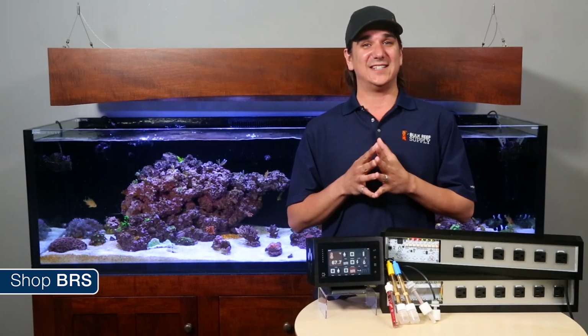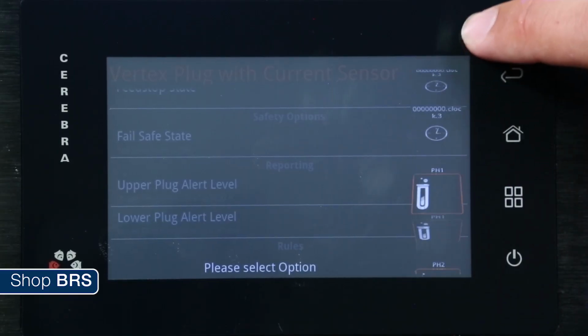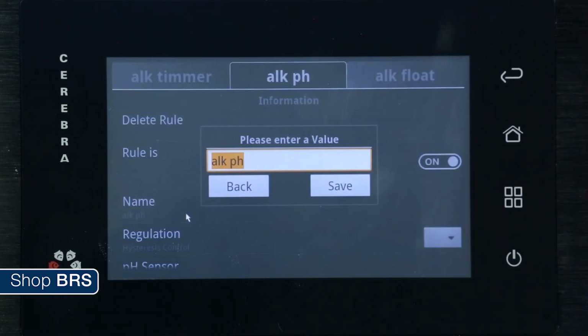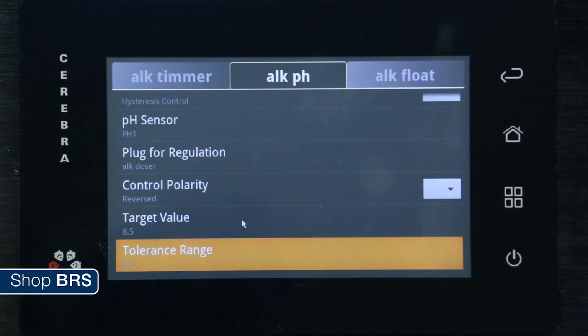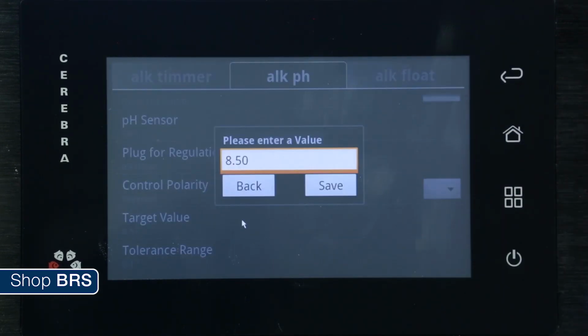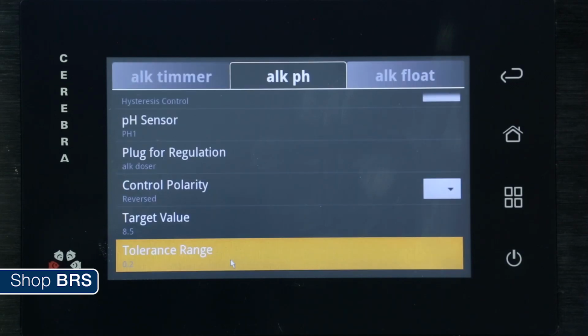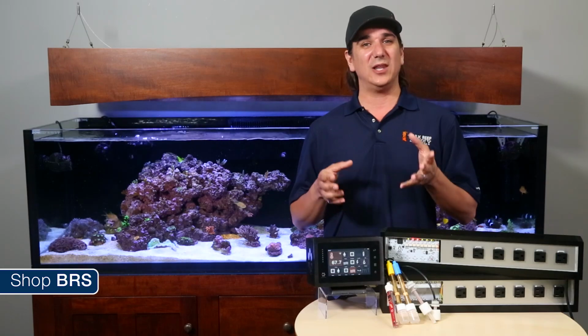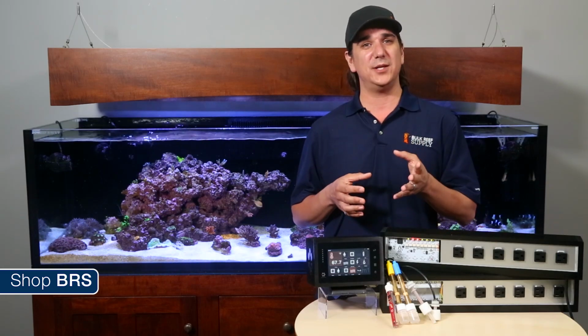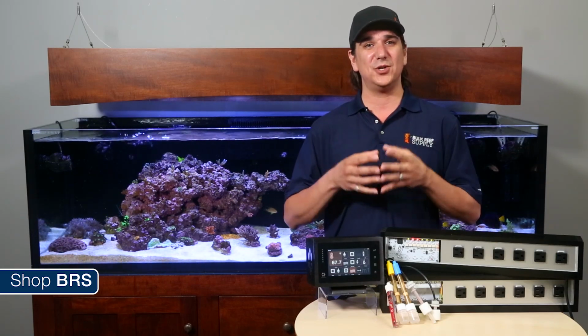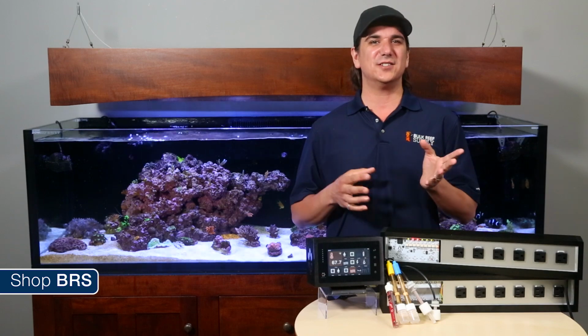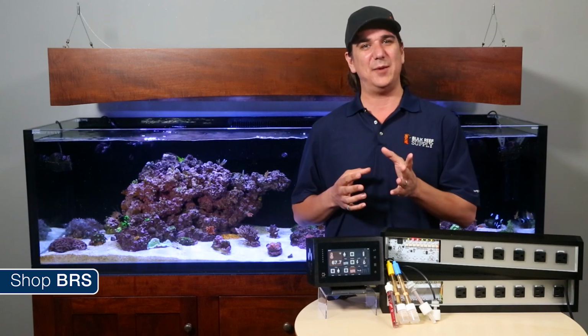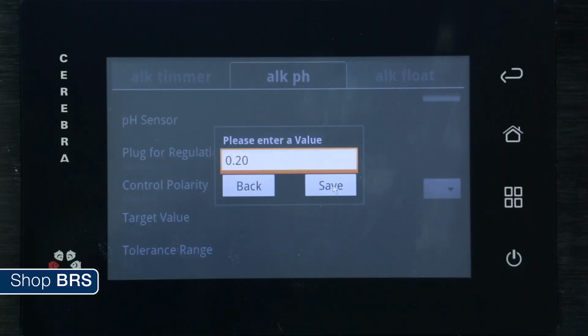It's almost the exact same. Create a new rule, select the pH probe as a sensor for the rule, name it alk pH and save, then your target value, which in this case might be 8.5. Rather than use hard to understand words like hysteresis, there's a tolerance range which we'll set to 0.2, meaning we'll allow the pH to drop 0.2 points or back down to 8.3 before turning the doser back on, so the outlet doesn't switch on and off constantly right at 8.5. You might want to set it higher in some cases.